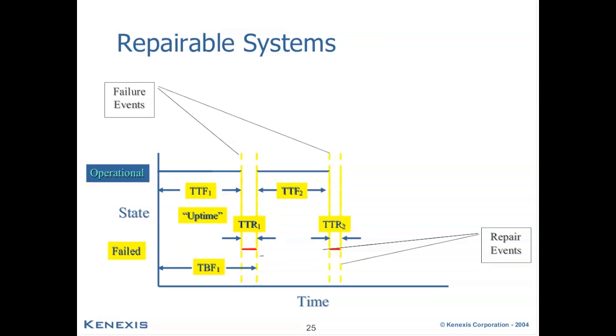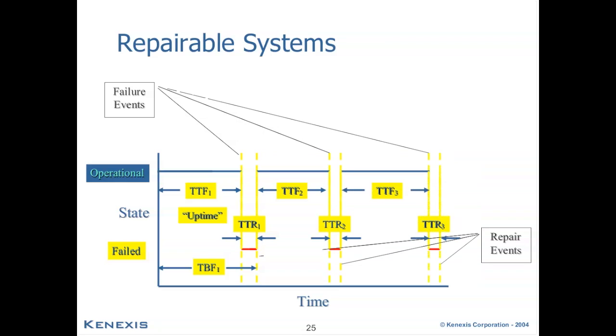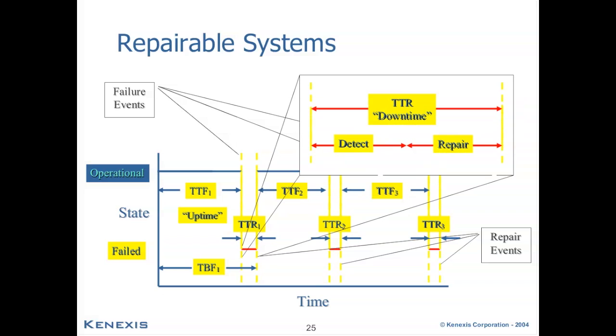And over the lifetime of the instrument, you should expect that the instrument will experience several similar patterns of time, failure, and downtime. It's the averages of these occurrences that we'll use in order to determine the mean values of failure and repair time for the devices. Also to consider during the time of repair, as mentioned before, is the amount of time it takes to first detect the failure before repair, which is added on to the total downtime.